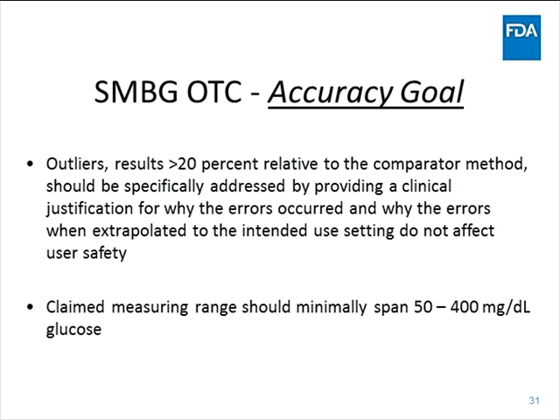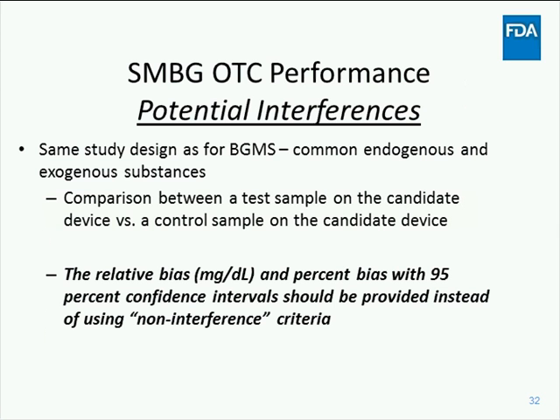We understand that some SMBG devices may not be able to reliably measure glucose at very low concentrations and meet this accuracy goal. However, we've heard from the clinical community that it could be acceptable for lay use to narrow the claimed measuring range based on the accuracy results so that readings as low as 20 milligrams per deciliter are not reported for a particular device. However, the measuring range for this intended use population should not be any more narrow than 50 to 400 milligrams per deciliter.